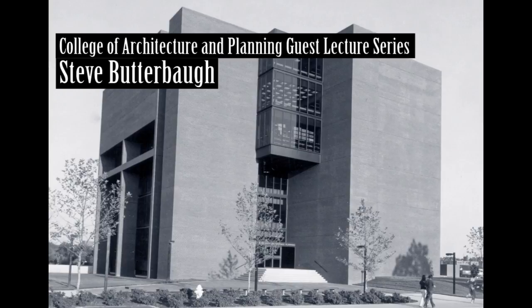The final step is to take the 3 bits of information and rank the proposed changes within each. What is the order from least to most expensive initial cost? In the Army's case, removing 767 lights was least expensive. Operating the surgery air handler intermittently was second. Replacing the windows was third, and buying a small air handler for the emergency room was fourth.